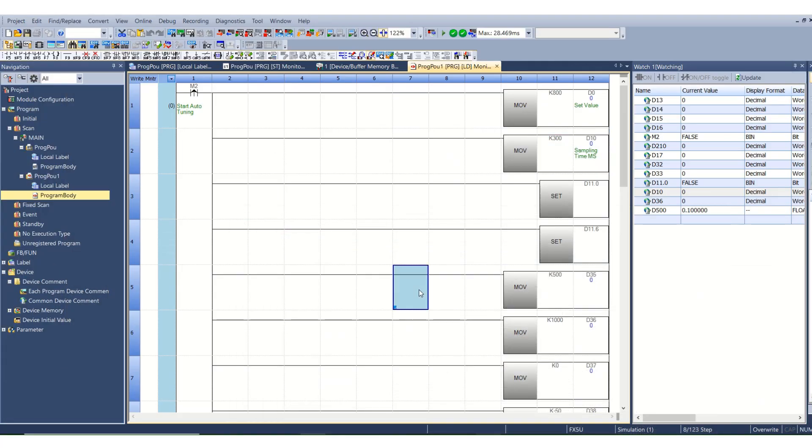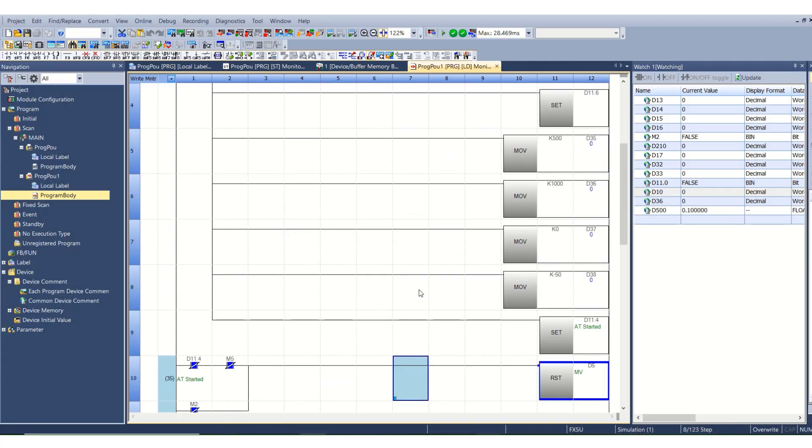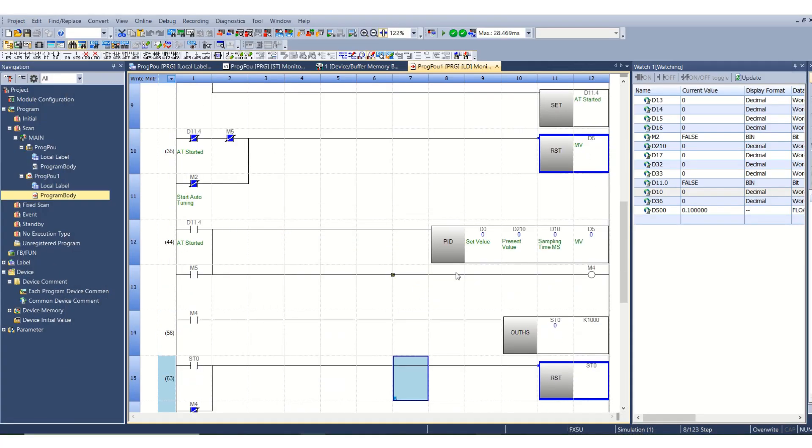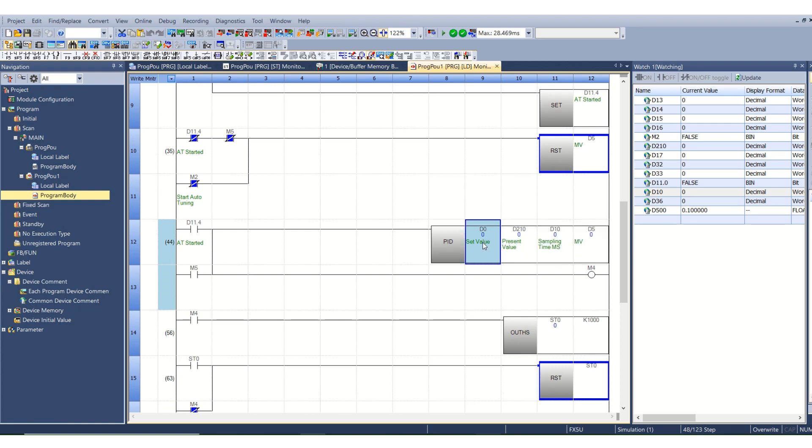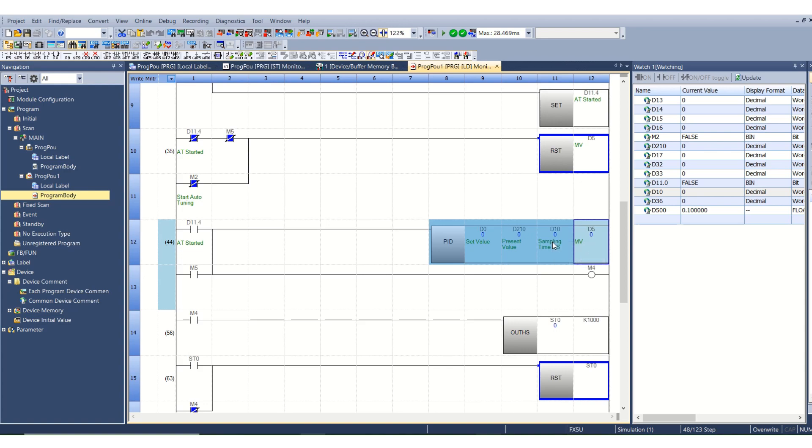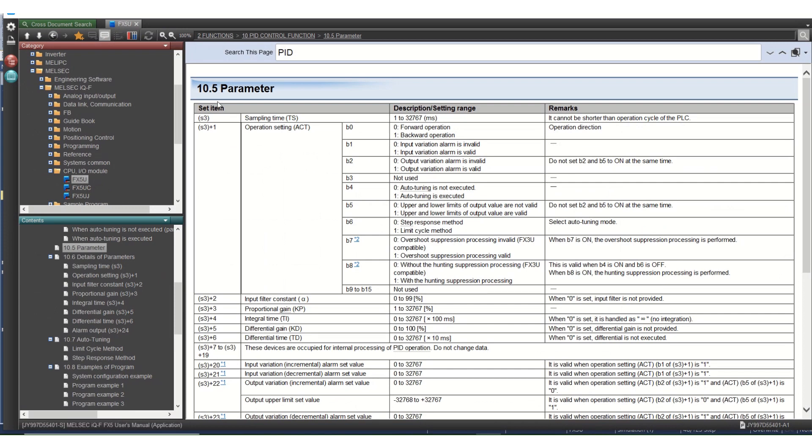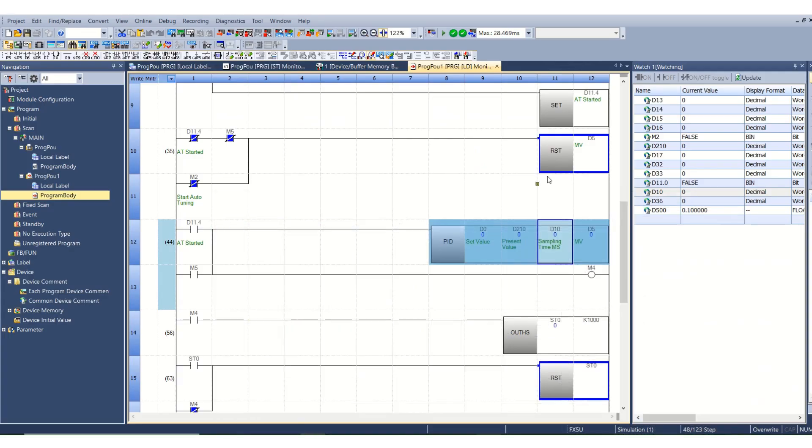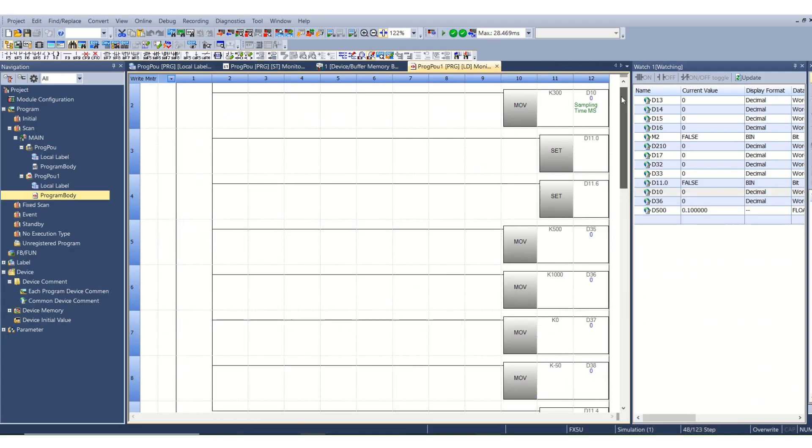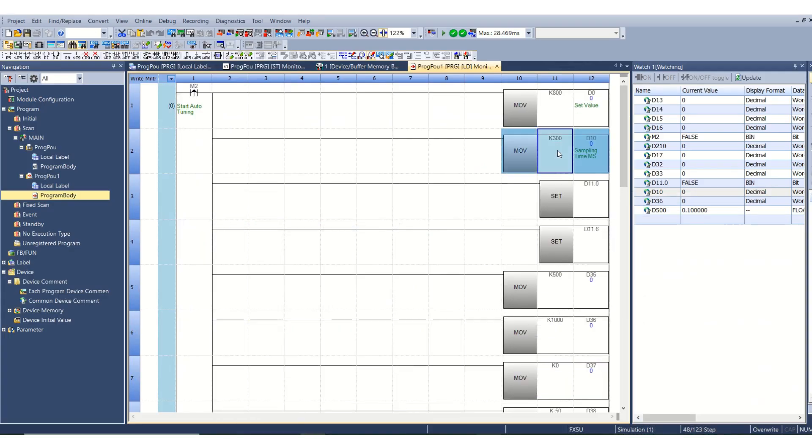I will show you the PID function block. Here it is used as D0, this is S1, S2, S3 and S4. Basically we need to set the parameters in D10, that means S3. In the manual parameter section is S3. First is sampling time. As I mentioned previously, the value here is 300 millisecond.